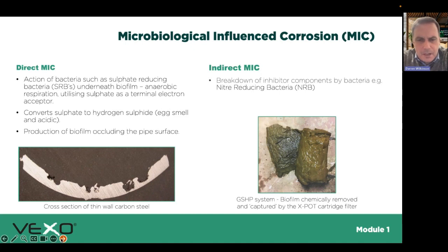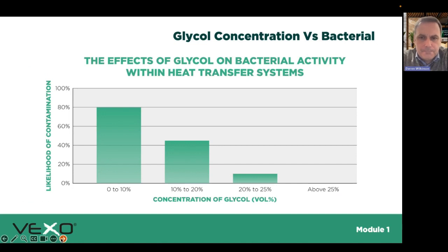But every October we fire it up, it's all gone. So it turns out it was biofilm and bacteria. So in terms of glycol concentration, as we're looking at ground source heat pump systems and other types of renewable systems that will require some level of antifreeze, some level of glycol, we've also got to consider that typically the industry considers anything above 25% volume by volume of dosed glycol antifreeze in a system. It's biostatic. You shouldn't expect to see any issues really.